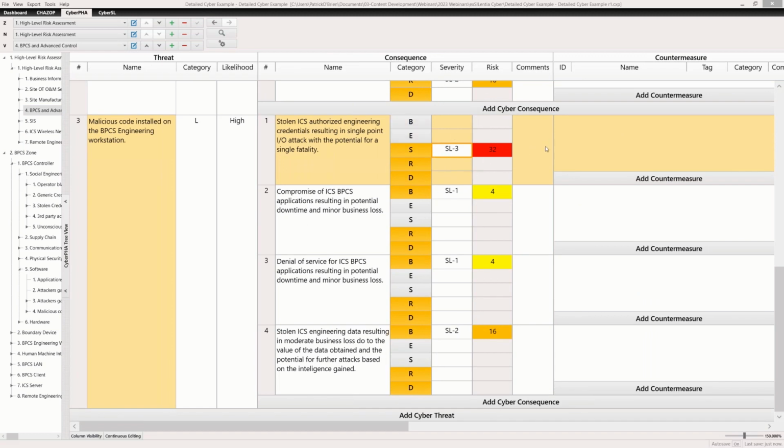When we think about this, a lot of manufacturers and OEMs are getting certified, and so they may be meeting the requirements for SL1 and SL2 primarily. But the number of systems that have gone through and really passed the requirements for SL3 and SL4 is still low, because there are significant changes and adjustments that go into meeting those higher levels.